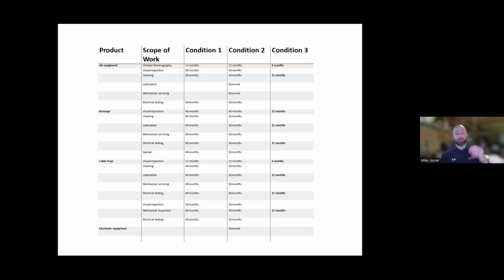The table is broken down on the left-hand side by type of equipment, whether it's busway, cable tray, switchboards, branch panels, or disconnects. The scope of work defines what needs to be done: infrared thermography, visual inspection, cleaning, lubrication, mechanical and electrical testing, and manufacturer spec testing as well, all throughout the scope. Then, depending on condition one, two, or three, it dictates the intervals.